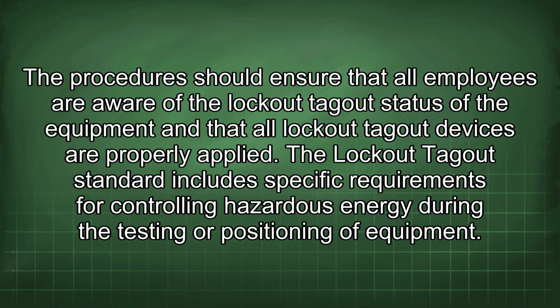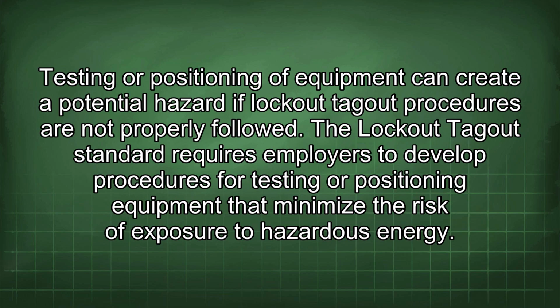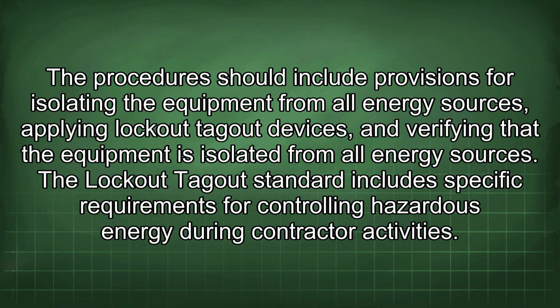The Lockout Tagout standard includes specific requirements for controlling hazardous energy during the testing or positioning of equipment. Testing or positioning of equipment can create a potential hazard if Lockout Tagout procedures are not properly followed. The Lockout Tagout standard requires employers to develop procedures for testing or positioning equipment that minimize the risk of exposure to hazardous energy. The procedures should include provisions for isolating the equipment from all energy sources, applying Lockout Tagout devices, and verifying that the equipment is isolated from all energy sources.